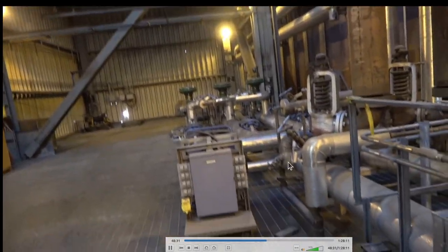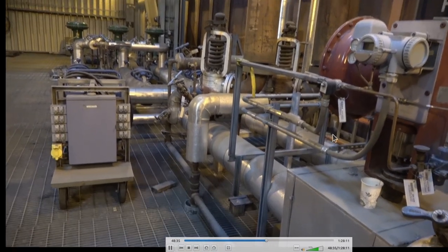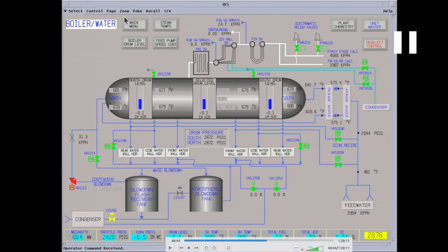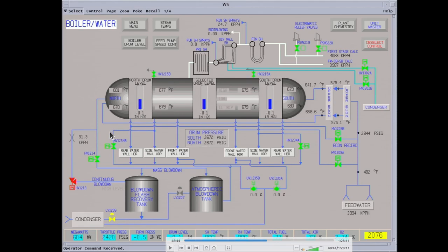More of the soot blow flow control and pressure control — this comes off the division wall header, pressure is let down, and these are flow control. Here's your boiler water and steam drum. Feed water heater 7 comes in to the lower economizer, upper economizer, then into the drum. Comes up through the primary superheat and division wall, then finishing superheat. You have your two safeties. A slipstream of water is blown off all the time as continuous blowdown — this goes back to the surface condenser and the polishers clean it up.